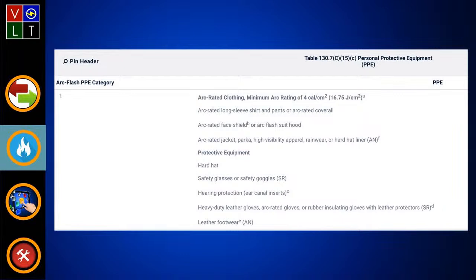The ARC-rated clothing at the top is fire resistant also, and then you drop down to the protective equipment. Again, the two tables in 70E: one table is for equipment you wear, and one is for equipment you do not wear, like climbing a ladder, laying down an insulating mat, or covering up material. If we ever do that course, we can go through all of it. Now let's go to the next one.